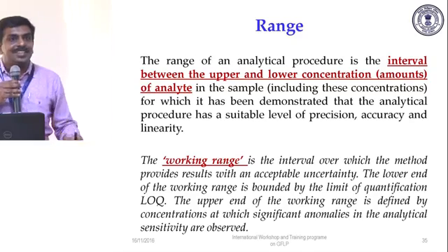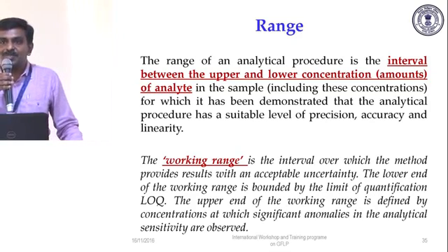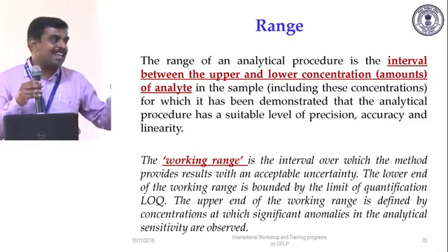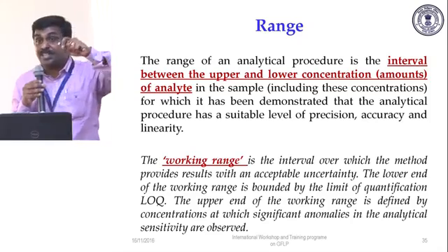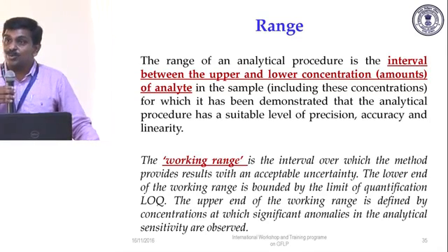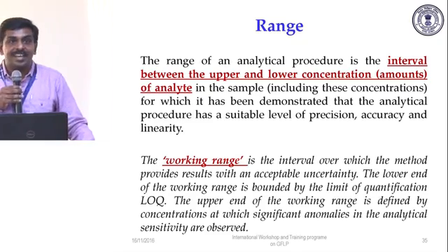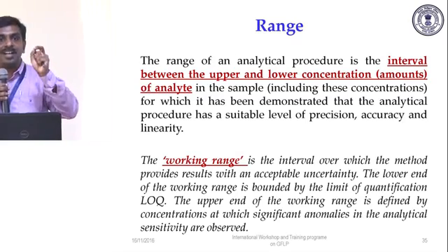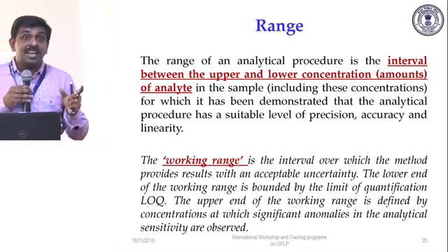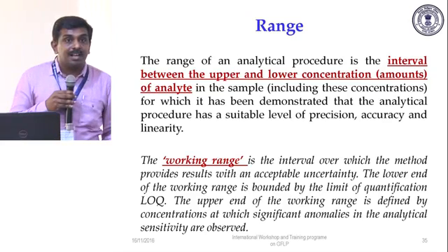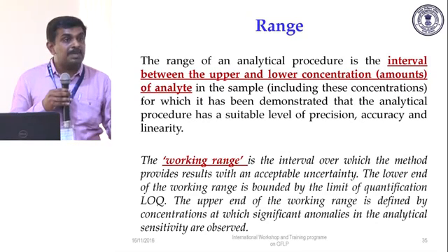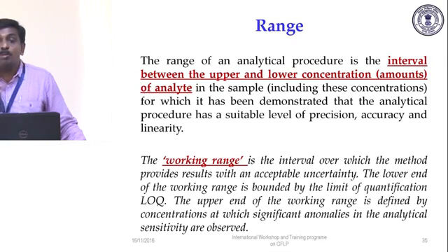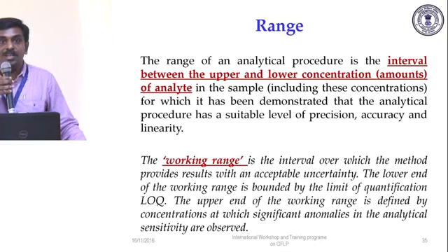But the highest range generally gets decided on the audit day. So you sit in one room and the quality manager tells, yeah, let us put 10. No, we have to put 20 because it is a customer requirement. No, let us put 30. So it's a discussion that day, and it's not a clearly defined highest range we give. I've seen labs putting 100 ppm as the highest range, 10 ppb to 100 ppm. See, how can it be tested? What instrument do you have? How much will you dilute it, if you have a provision to dilute it? Also how much?